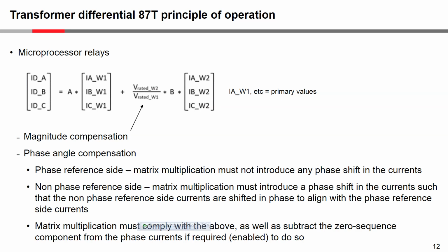And then, of course, the phase angle compensation. Remember that the phase reference side, whichever that is, the high or winding 1 side or the low or winding 2 side, the matrix multiplication must not introduce any phase shift. And for the other sides of the transformer, the non-phase reference sides, the matrix multiplication must introduce a phase shift in the currents, such that the non-phase reference side currents are shifted in phase to align with the phase reference side currents.